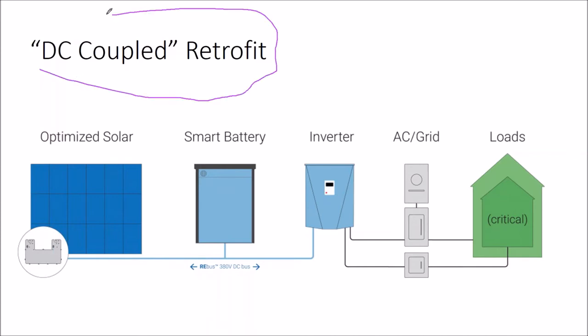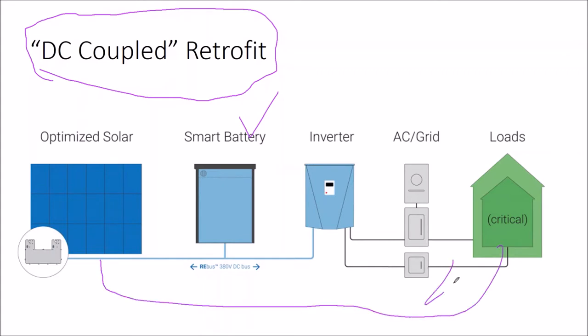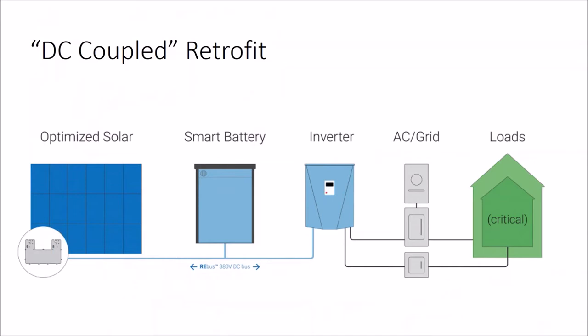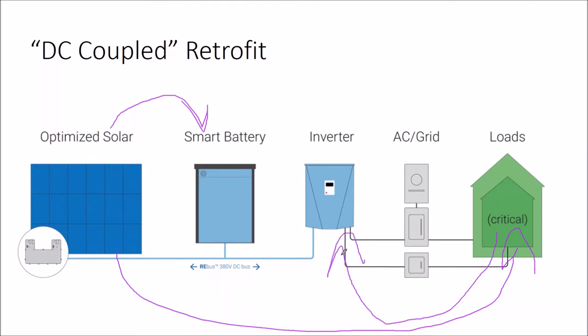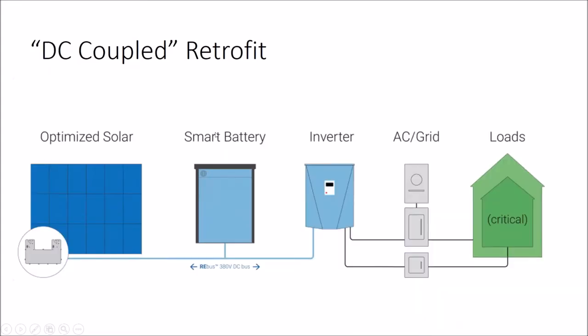Where DC coupling makes the most sense is if you're completely off-grid, because then you're always running off the battery—you're only running off solar for a couple of hours in the middle of the day. That solar array is so large that most of its energy goes into charging the battery bank back up. So in an off-grid home, it's more efficient to go directly into the battery rather than from the solar array into the service panel, then into the battery inverter, then into the batteries, and then back into the load when you need it. There's all this debate about AC coupling versus DC coupling, and I don't really think it should be a debate.